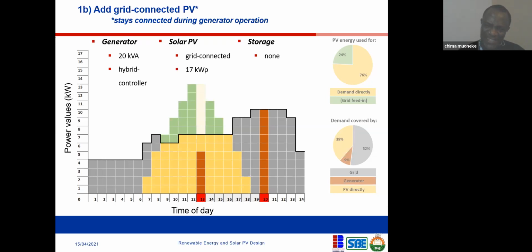Your solar system cannot reliably supply all your required energy. Imagine there is no generator, you're just running your solar system, and a cloud or shadow passes over your solar panel. That means the output from that solar panel will just drop. What happens if you have a critical load connected to that solar panel? It will go off automatically. So you don't want your critical equipment to go off. You still need to put your generator on, so that if the output from your solar system drops, your generator can continue and cover that shortfall.